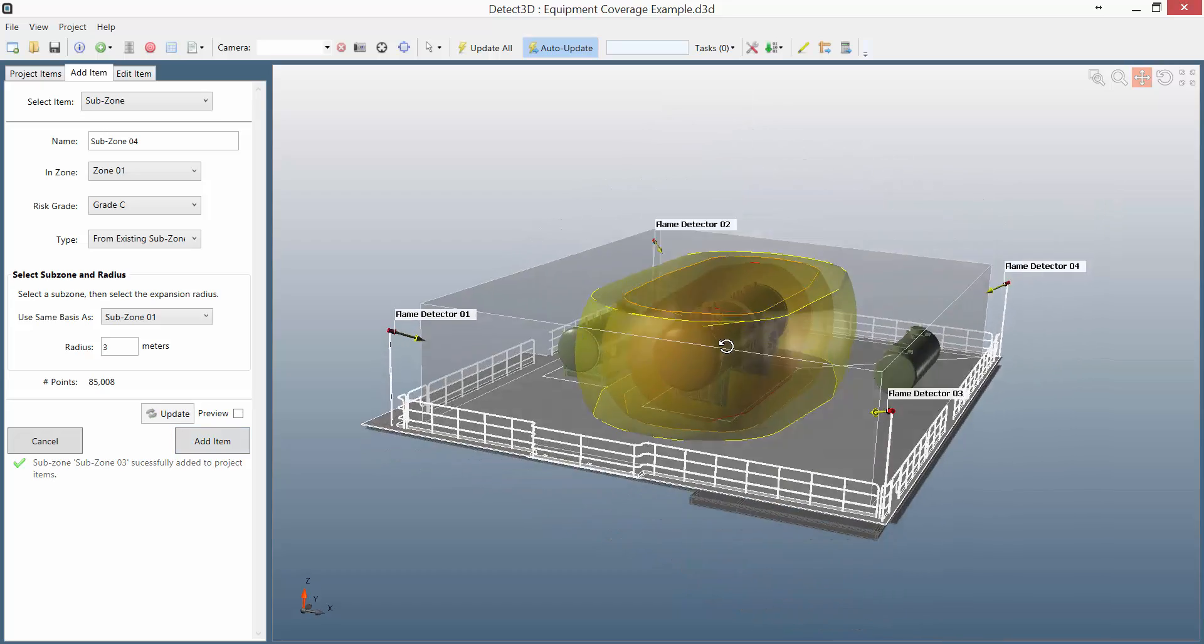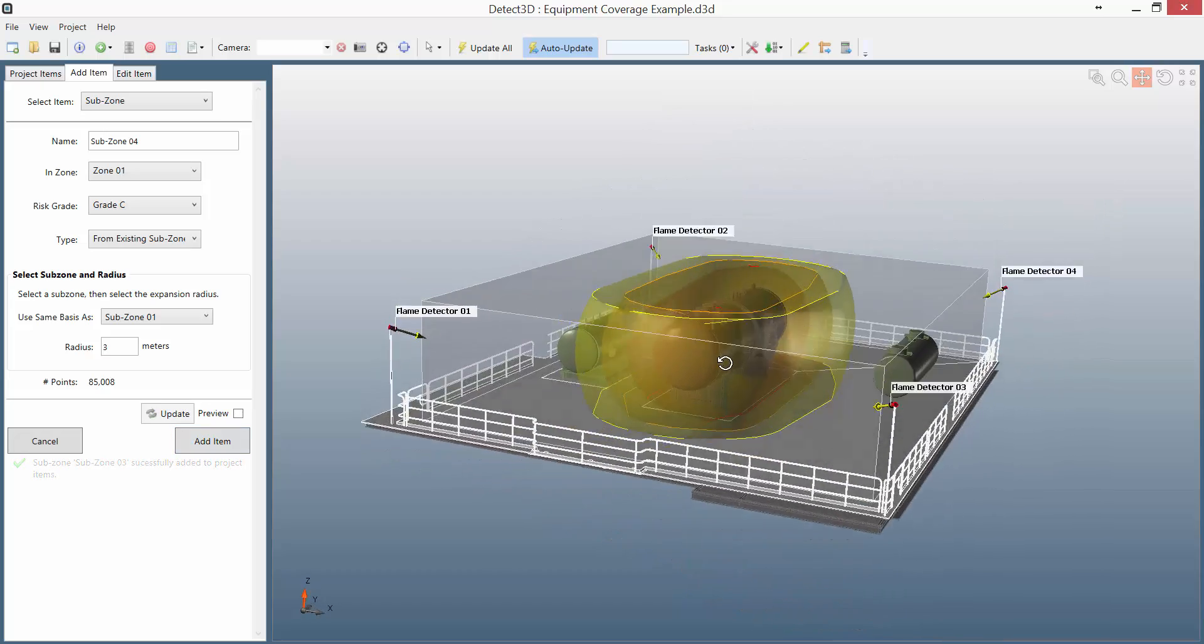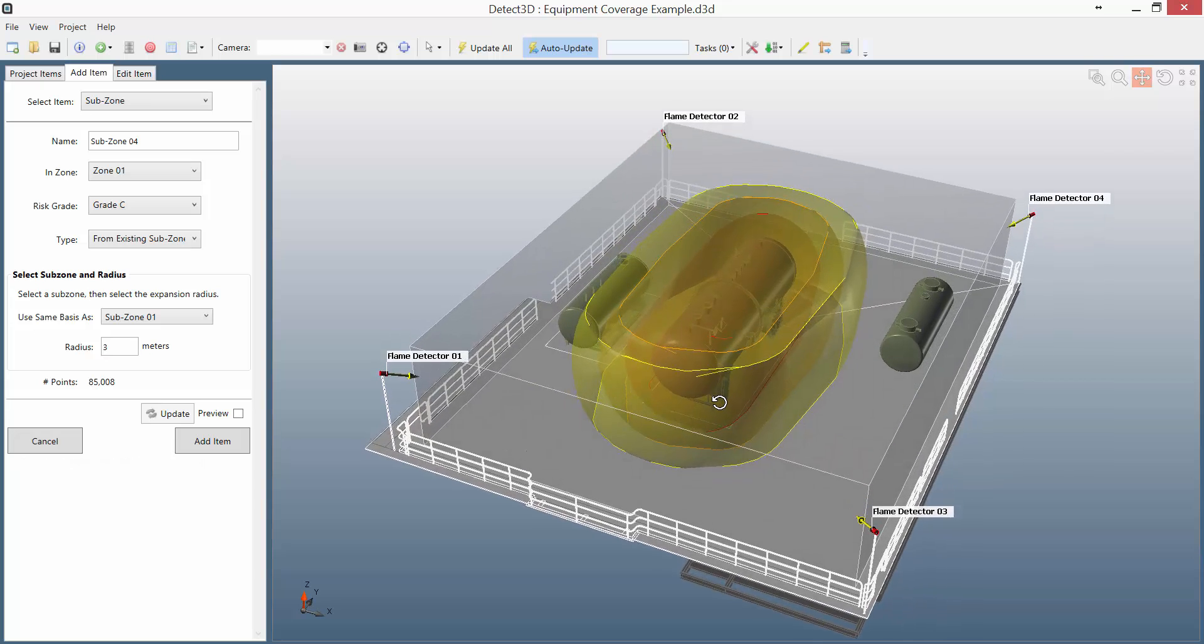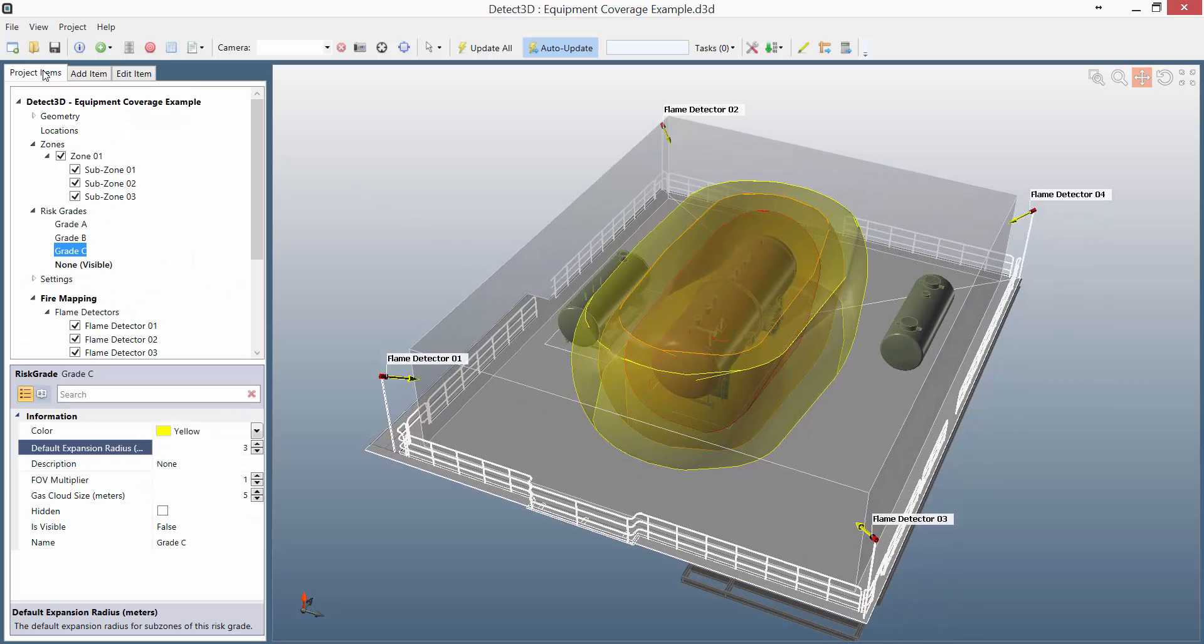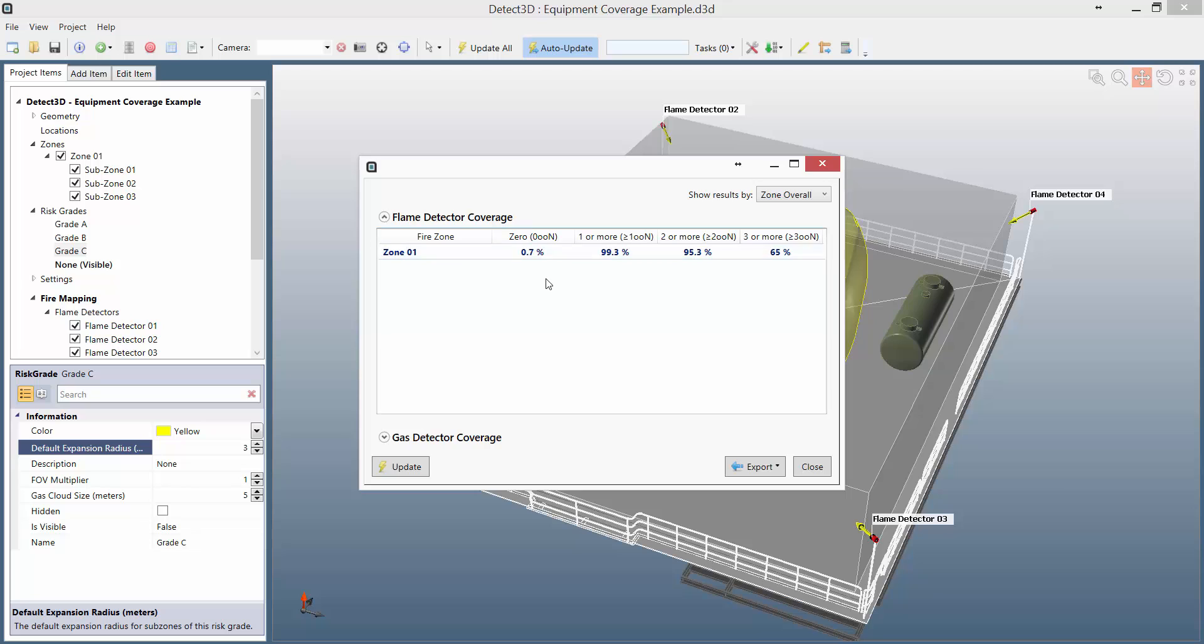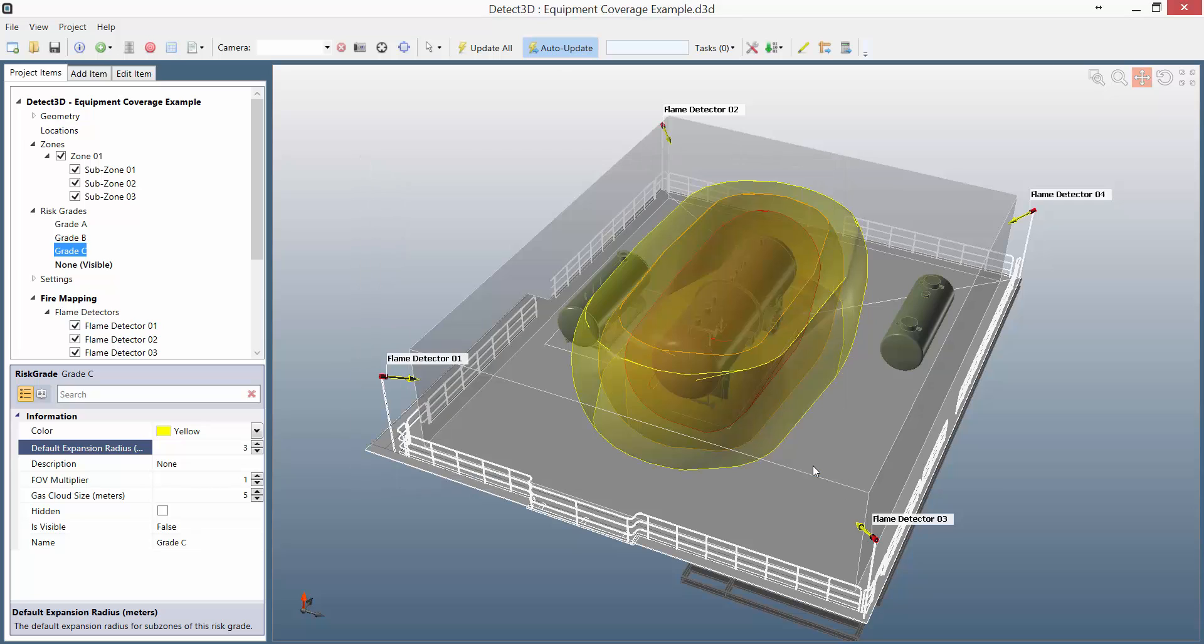You can see the three subzones I defined around the equipment limited by the grey zone, and I can also see their coverage. The overall coverage is still for 10kW. Grade A is for 1kW, B is for a 5kW, and C is 10kW fires. I can also see the subzones around the equipment, and see the individual coverages for each fire around that equipment item.